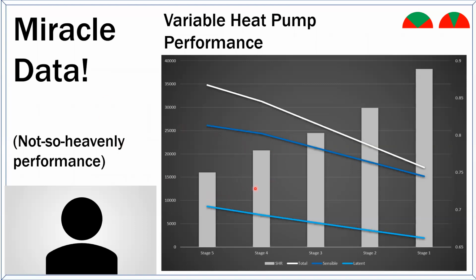But as it ramps down, now I've got 0.78, now I've got a little close to 0.8, now I'm getting 0.83. But by the time I'm at the end, I only have about 10, 12% of my system's capacity controlling moisture at low stage. So the more it ramps down and the more it load matches, the less moisture removal it's doing.